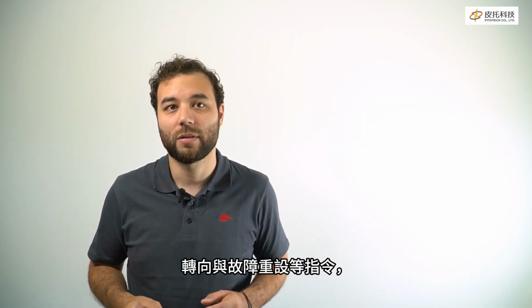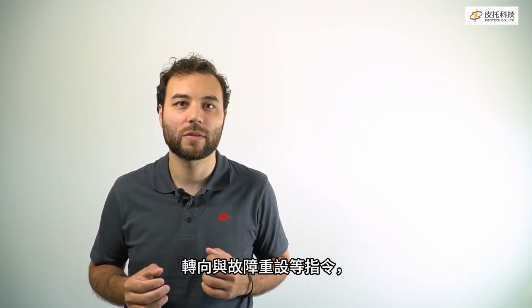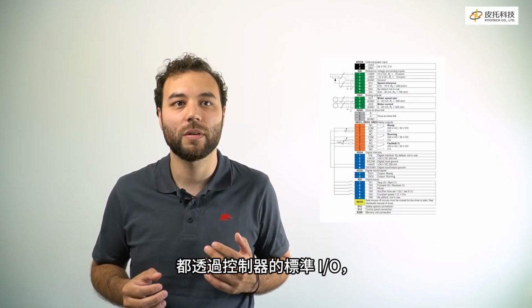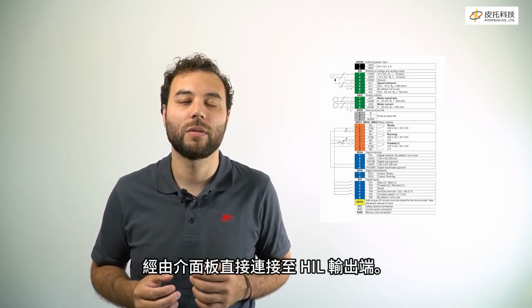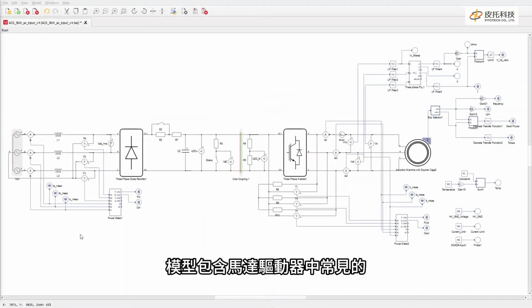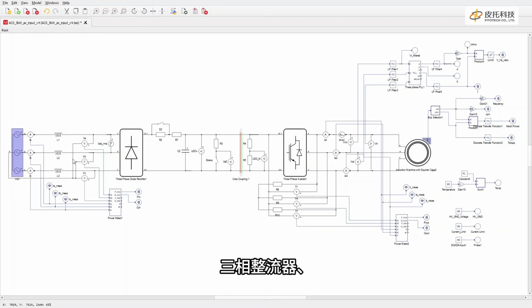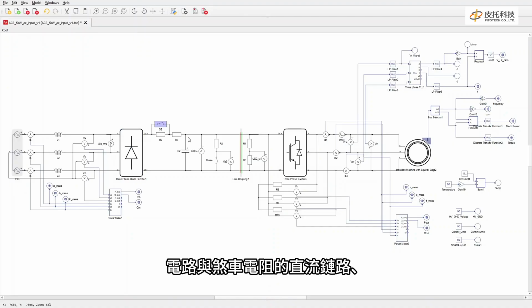Start-stop, direction, and reset commands are accessed through the controller's standard I/O interface directly connected to the HIL outputs. The model comprehends all common motor drive power circuits, including the three-phase voltage source, the three-phase rectifier, the DC link with inrush circuit and braking resistor, the three-phase inverter, and the squirrel cage induction motor.